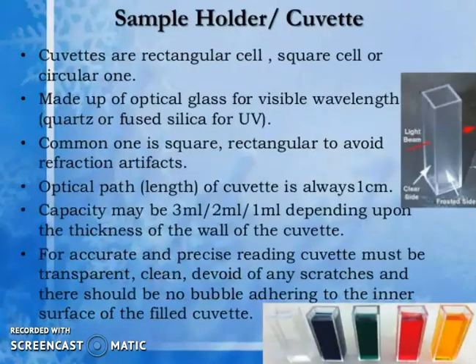Cuvettes (sample holders): cuvettes are rectangular, square, or circular cells made of optical glass for visible wavelength, or quartz/fused silica for UV. The common shape is square or rectangular to avoid refraction artifacts. The optical path length is always 1 cm; capacity may be 3 ml, 2 ml, or 1 ml depending on the wall thickness. For accurate readings, cuvettes must be transparent, clean, devoid of scratches, and free of bubbles adhering to the inner surface.